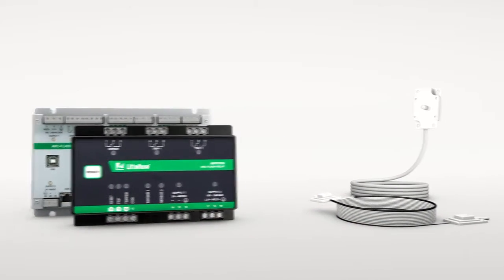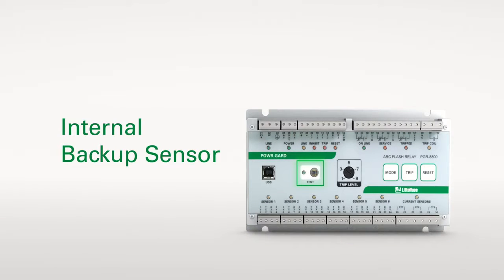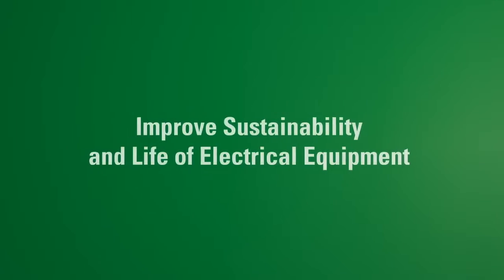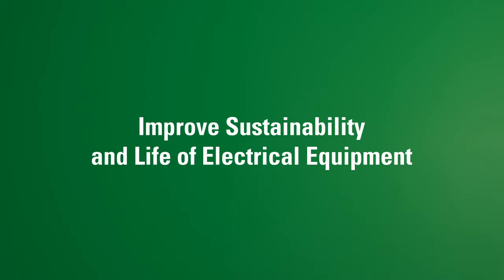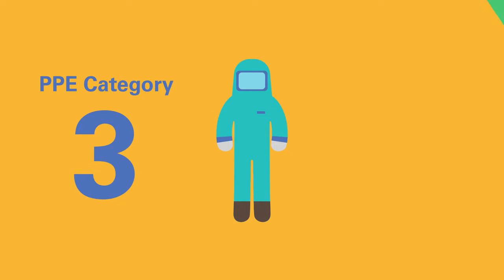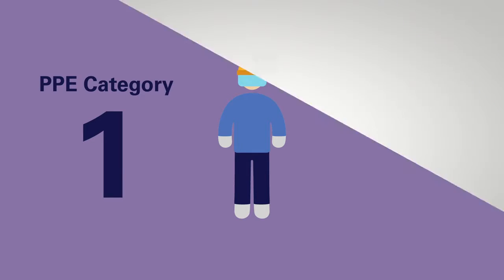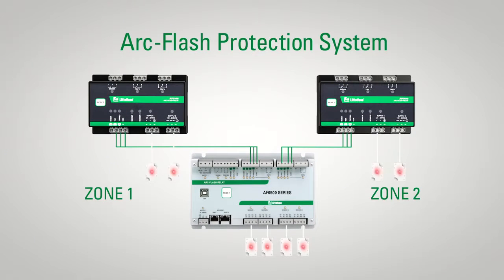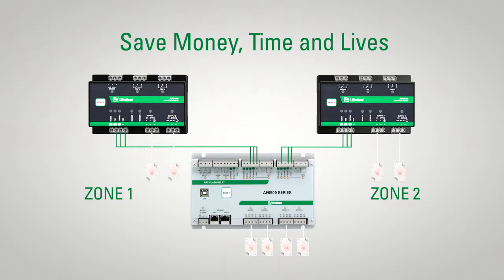Littelfuse arc flash relays have backup trip paths, so if one fails, the other is still protecting. Arc flash relays improve sustainability and life of electrical equipment. They can also help lower the PPE category of protected equipment. An arc flash relay is an integral part of an arc flash protection system that can minimize damage, save money, time, and lives.